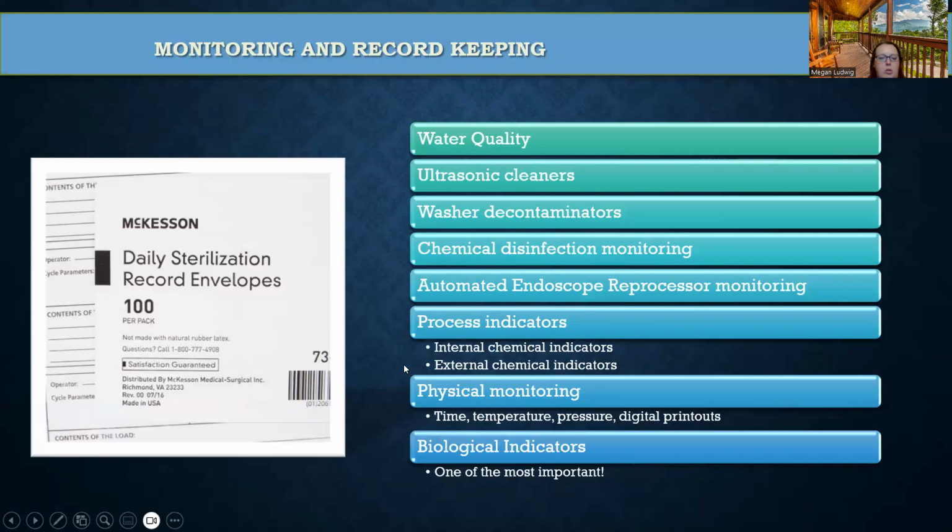So if we're talking about that rigid casket container for instruments, there will be that strip on the inside, usually turns black or maybe green. That's your internal chemical indicator. And on the outside, there's going to be usually one on each side that goes through a little hole, and when you pop open the sides, it cracks it. So it's like a seal. You would know if it's been tampered with. So it has two purposes, really.